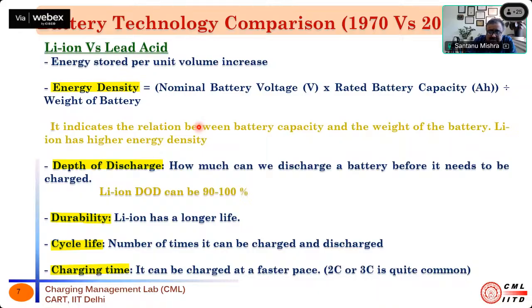The same is not true for lead acid battery. If you discharge the lead acid battery to a very low state of charge, then charging it back again, it will do that, but it cannot do it many times. Actually, depth of discharge is not that good for a lead acid battery, and going for a higher depth of discharge, that means discharging a lead acid battery to a very low voltage, doesn't increase the life of the battery. That's why, as far as depth of discharge is concerned, lithium ion battery has excellent depth of discharge, and it can do that many times over its lifetime.